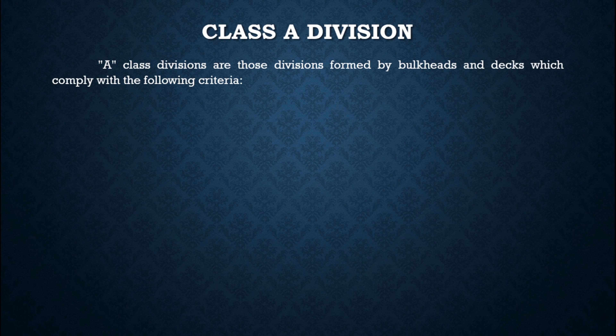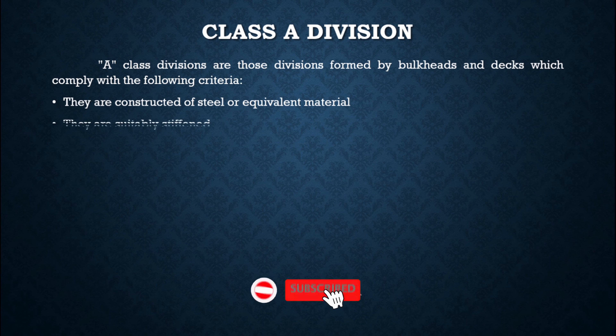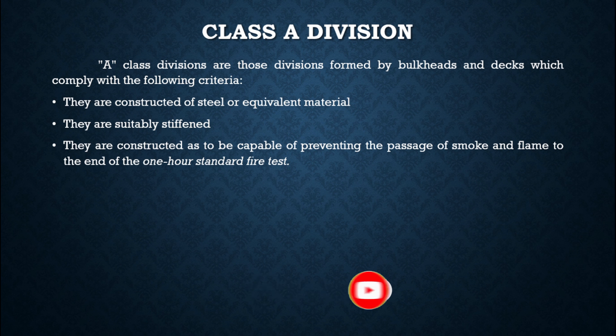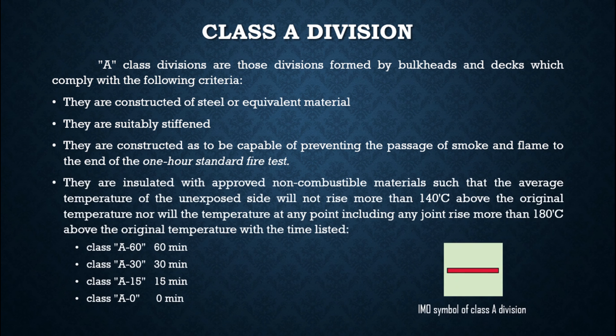Class A divisions are those formed by bulkheads and decks which comply with the following criteria: they are constructed of steel or equivalent material; they are constructed so as to be capable of preventing the passage of smoke and flame to the end of a one-hour standard fire test, where the standard bulkhead is exposed to fire for one hour and its properties are assessed on that basis.